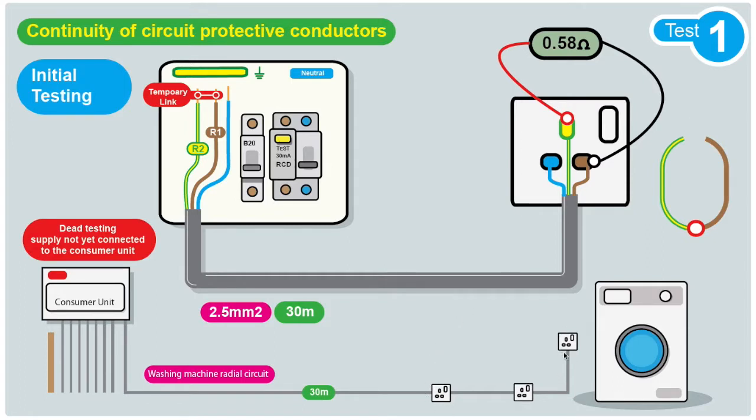It's quite a simple test. We link these out and take a reading at each socket with our test meter. In this case we've got a reading of 0.58 ohms at the furthest point, and we call this our R1 plus R2.